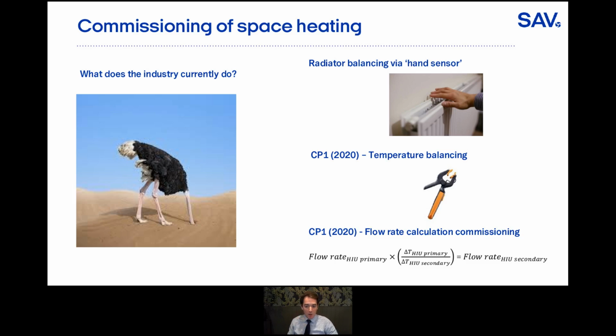As such, CP1 is then improving that process and saying, actually, the way that we can do it is by temperature balancing. For temperature balancing, you have these external clamp-on temperature probes, and you can join them onto the pipework either at the radiators or at the HIU, and you can see those flow and return temperatures, and try and balance your radiator system to that.